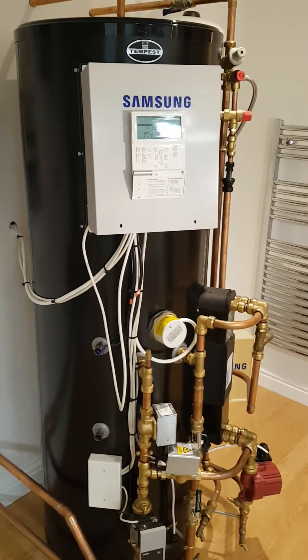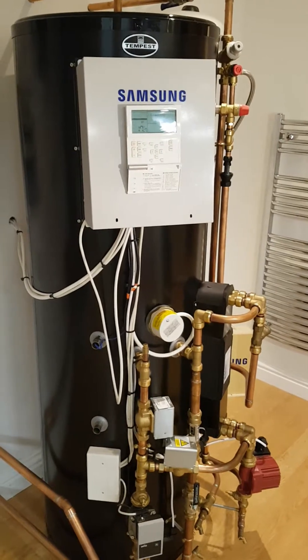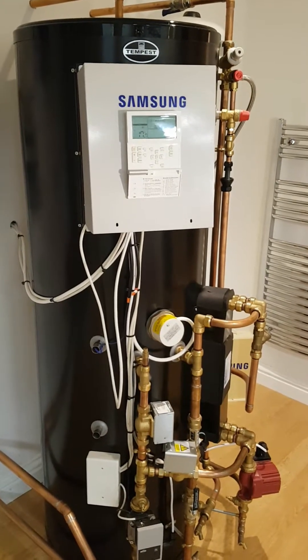In this video I want to look at fault code E464, which is one of the most complex fault codes you get on these systems. E464 means the unit has been working too hard, so we need to check a few things that might cause the unit to overheat.